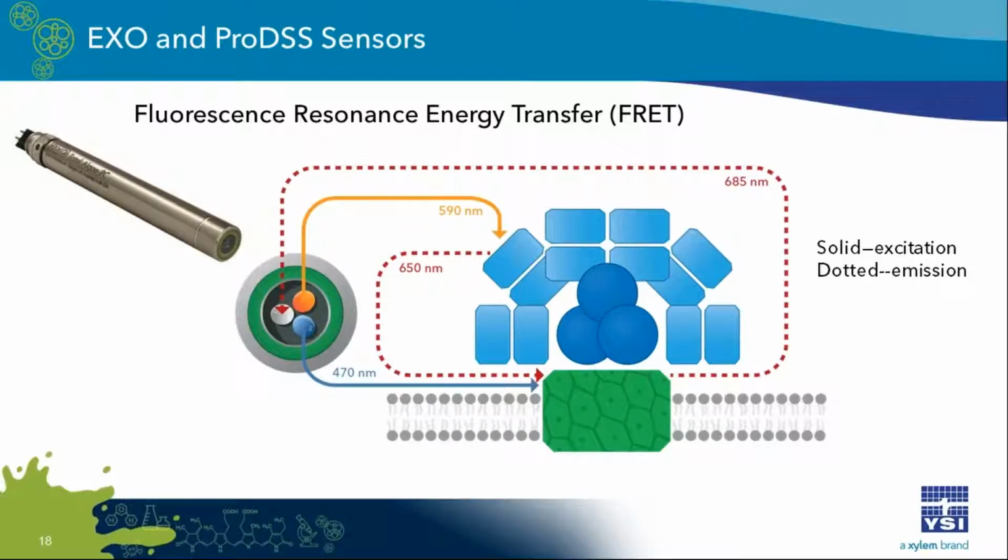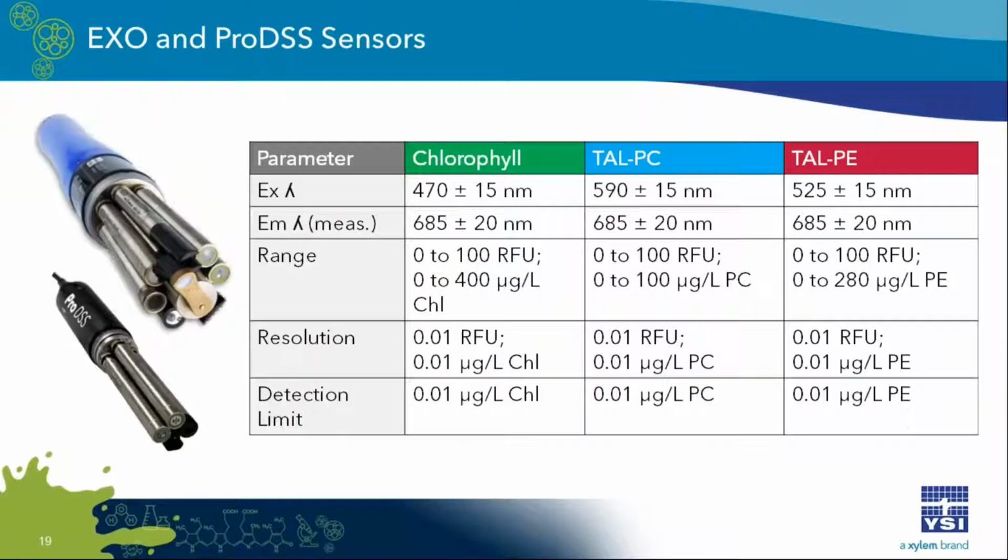And it's when one LED is on and the other is turned off, and vice versa, we have algorithms inside the sensor that allow you then to distinguish whether what is being detected is coming from chlorophyll or whether it is coming from phycocyanin. That's where the brilliant folks in YSI's R&D do their magic in the sensor, developing and applying those algorithms in our firmware. So this really gives you a different profile for performance.